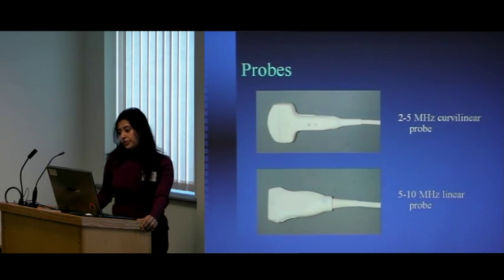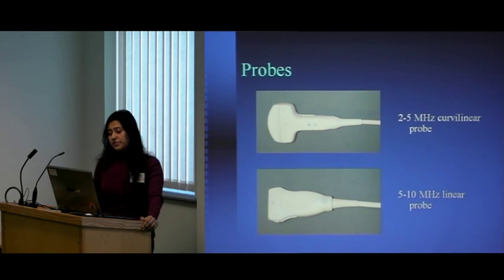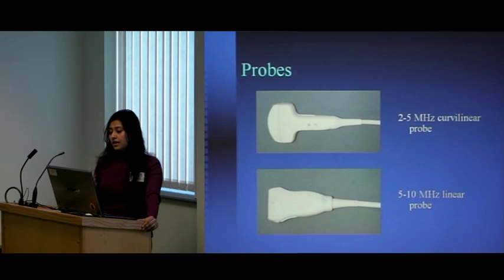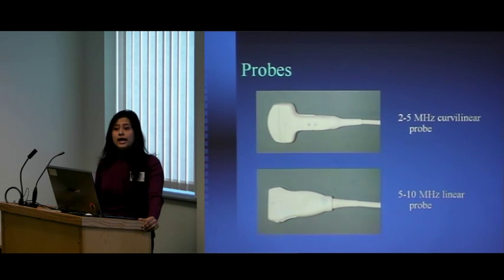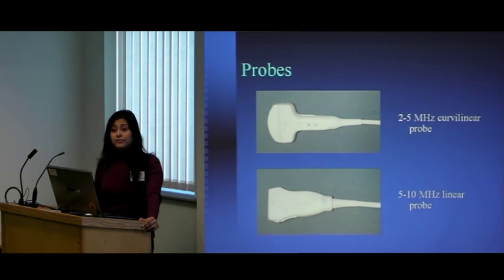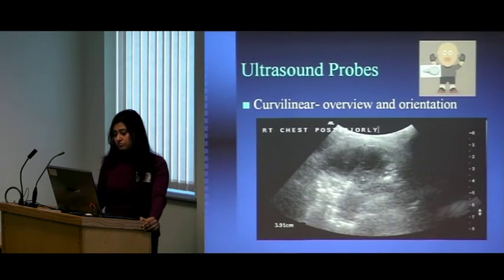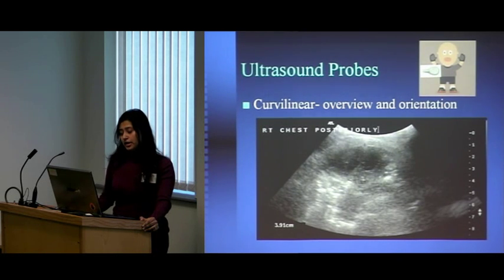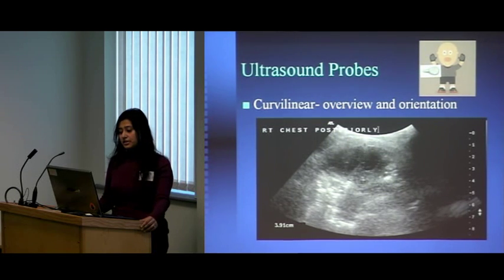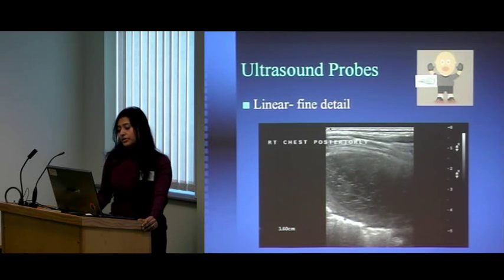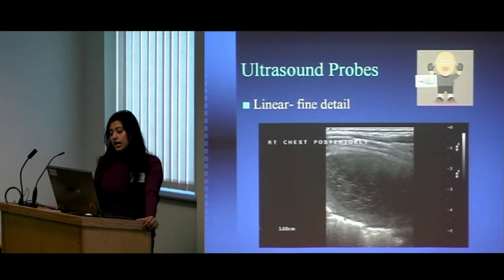These are the probes: the first is the 2 to 5 megahertz curvilinear probe used commonly. Because it has lower frequency you can see deeper structures, and the sector scan allows a wide field of view through a narrow acoustic window. The second probe, the higher-frequency linear probe, is used to look at the chest wall or pleura in more detail. With the curvilinear probe you can see an effusion with some echogenic material, but with the linear probe you can see more detail, including echogenic septations, loculations, and particles.